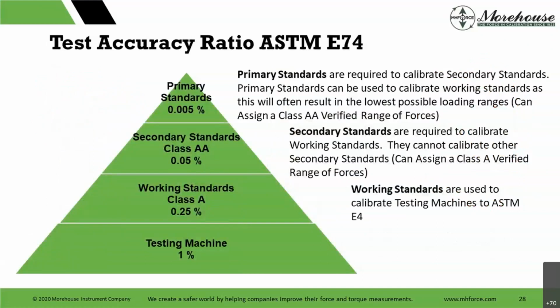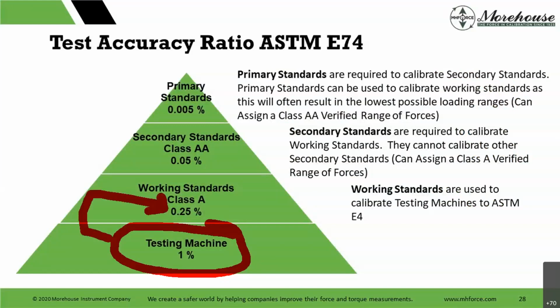And here's that pyramid that I wanted to draw. This is the only situation where TUR can work, because it's built up, right? This is our end user process measurement testing machine. The standard is basically saying, to calibrate this, I need a standard that's 0.25%. And then to calibrate that standard, I need a standard that's 0.05%, and it all starts with deadweight primary standards. You can't keep going and going. There are only four levels, and there will only ever be four levels, because this standard is written to support the E4 standard, which is the verification of the testing machines that are used to keep the bridges, cars, everything safe for you.